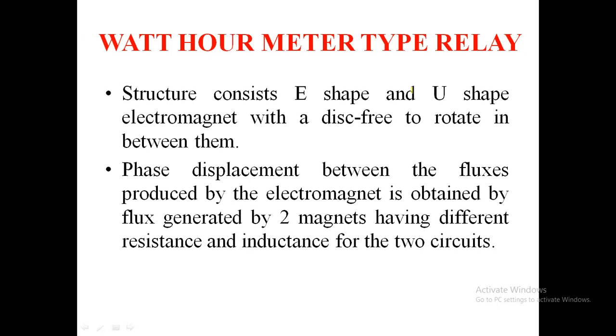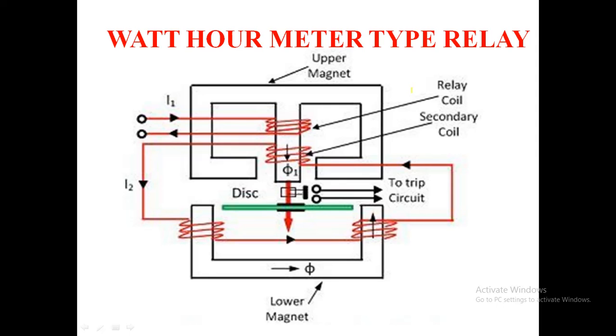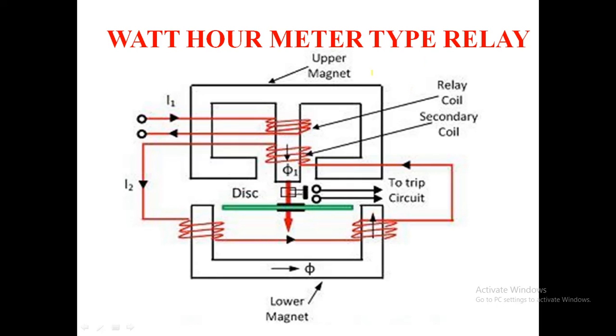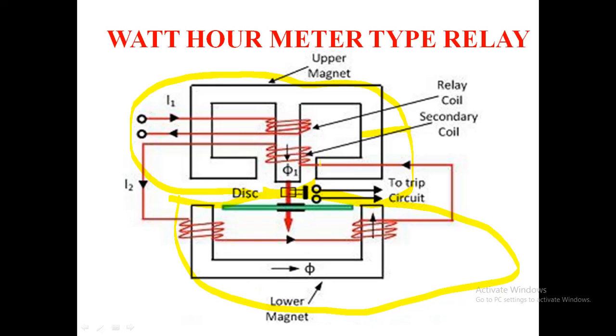Next, coming to the watt-meter relay. The main feature is that its operation can be controlled by opening and closing the secondary winding circuit. If the secondary winding is opened, no torque will be developed. The main structure consists of an E-shape and a U-shape electromagnet with a disk free to rotate in between. The E-shape forms the upper magnet and the U-shape forms the lower magnet.